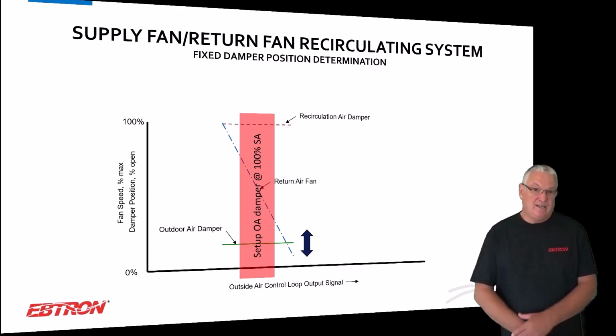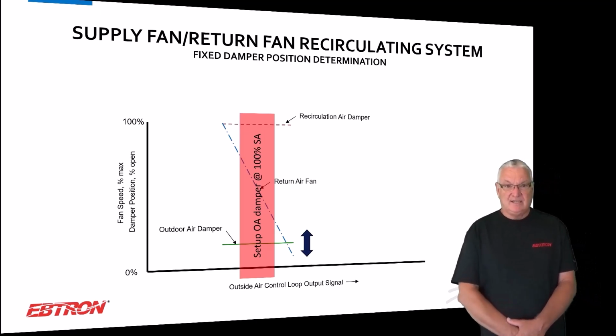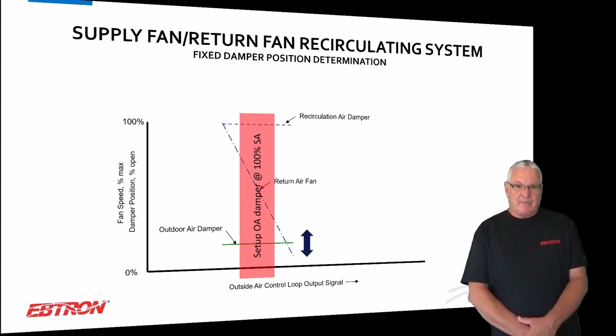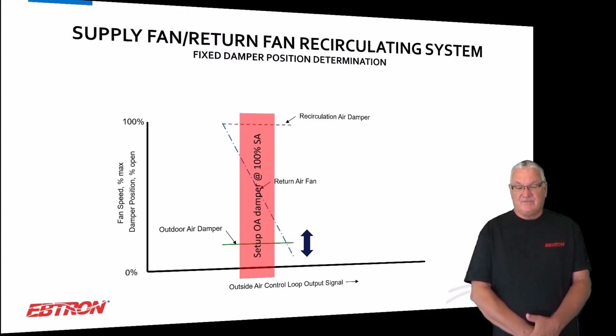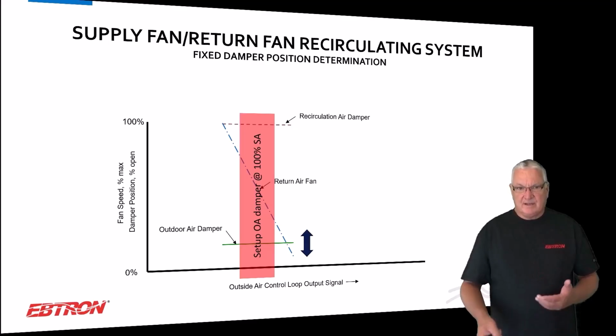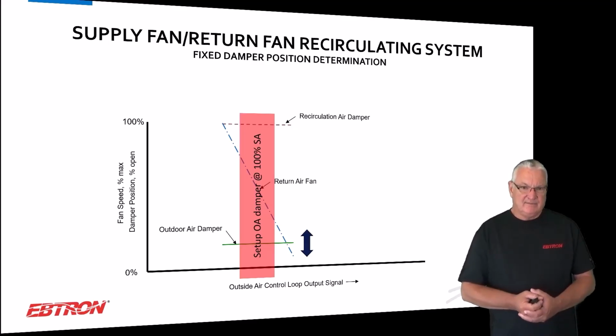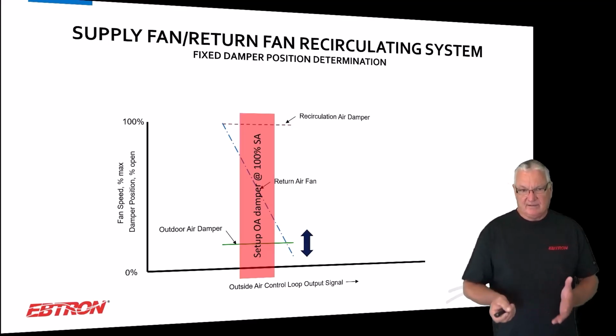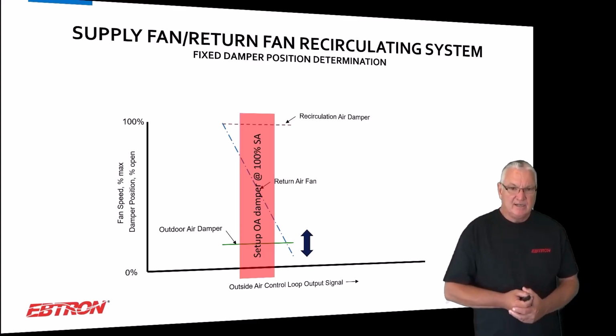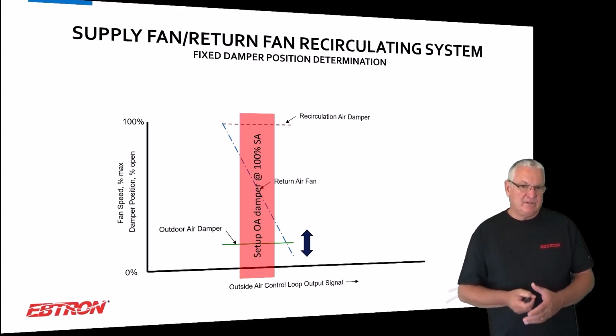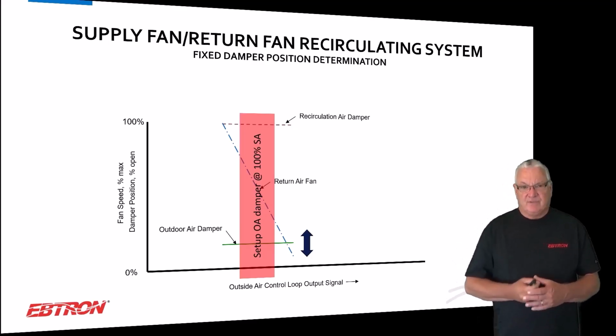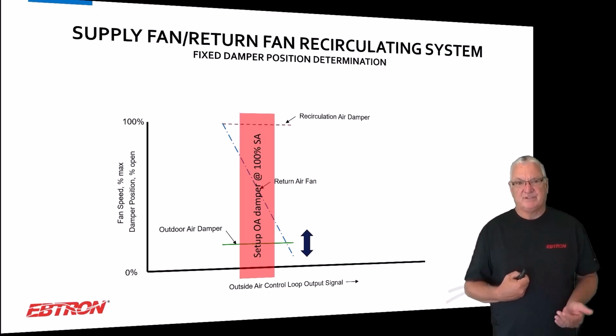The way we find it is, we set the system up basically at 100% supply air. If it's VAV, all the boxes are wide open. We set the return fan to somewhere around 80% of its speed. It's anywhere in that red area that I'm showing there, okay, to give you some play on both sides. And we used the EBTRON airflow meter to dial in what that minimum position is.